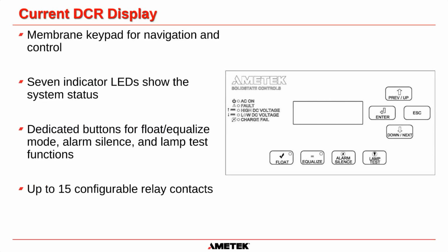Now I'm going to talk about our current DCR display. We use a membrane keypad with 8 buttons to navigate and control the DCR. There are 7 indicator lights on this front panel that give you the system status. There are dedicated buttons for the float and equalize mode transitions, an alarm silence button and a lamp test button. The DCR display allows up to 15 configurable dry relay contacts to give the status of the system and any active alarms.